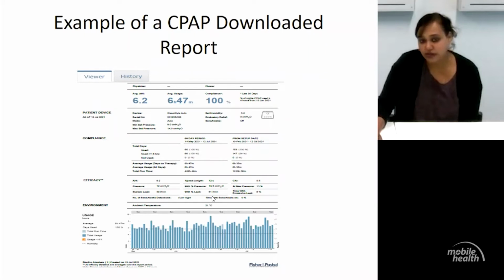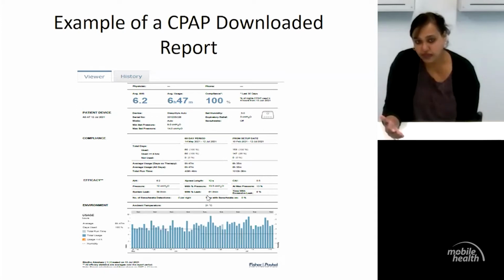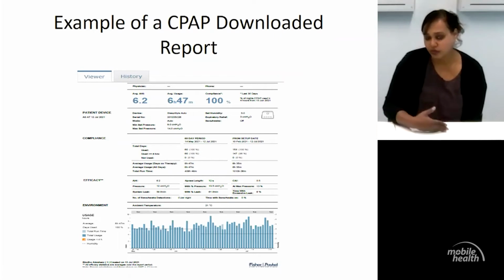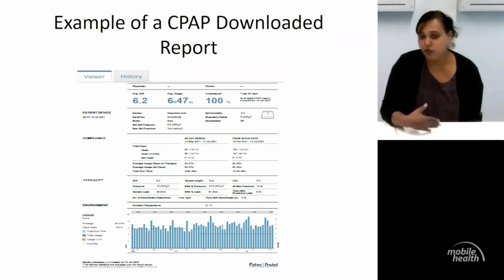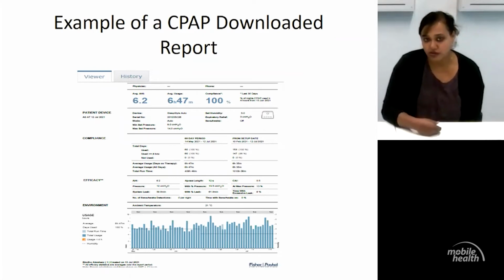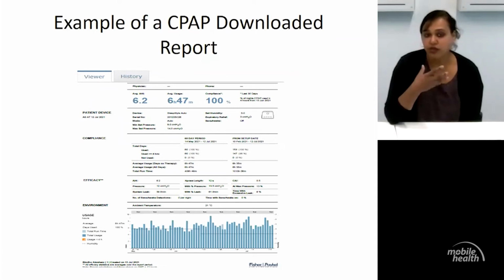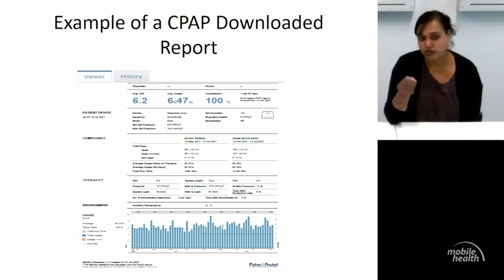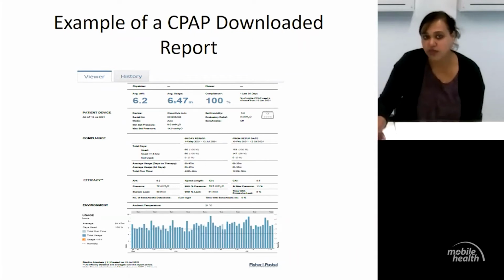So mask leak down here, it gives us a number, and up to a 24 is a normal leak level for any machine, any mask that they might have. But if we see something like 80, 90, or even 100 or more liters per minute leak, then we know that this patient would be having problems with having lots of noise coming out of the machine, as they normally say, or the water blowing into their face, or waking up with headaches in the morning. So depending on their symptom when they phone us, we would look and check all of the reports to see what makes sense. Are they leaking a lot of air, or is it the machine making a lot of sound?